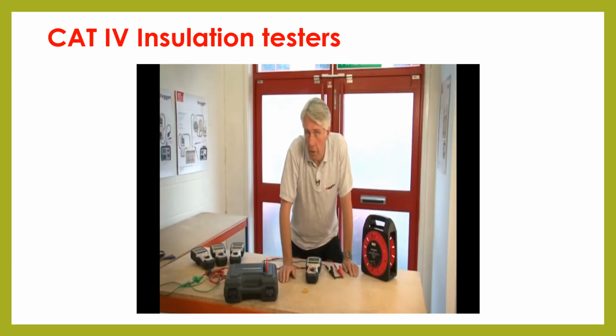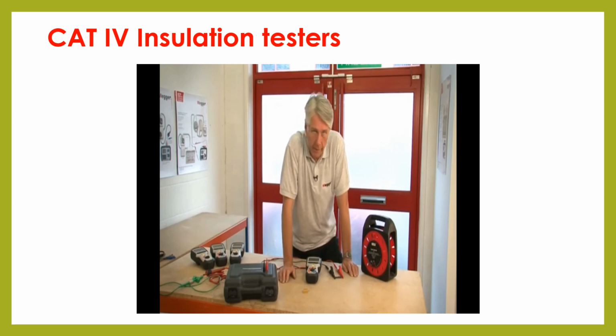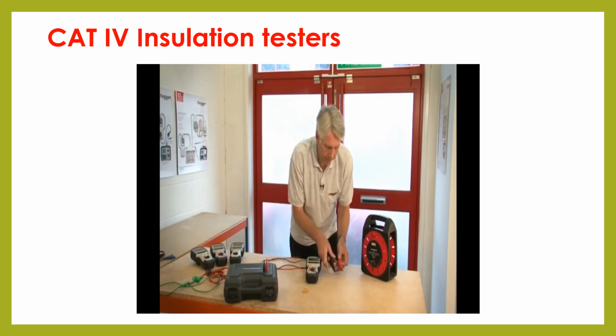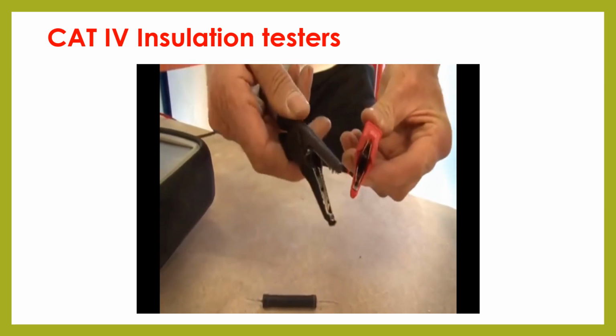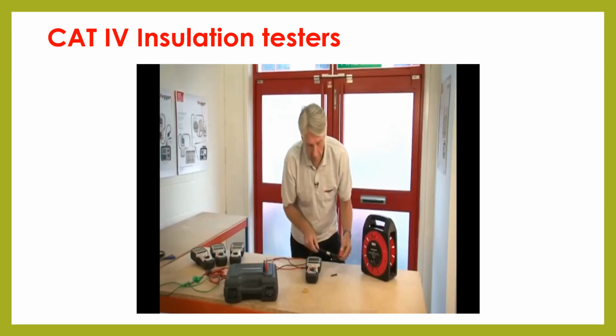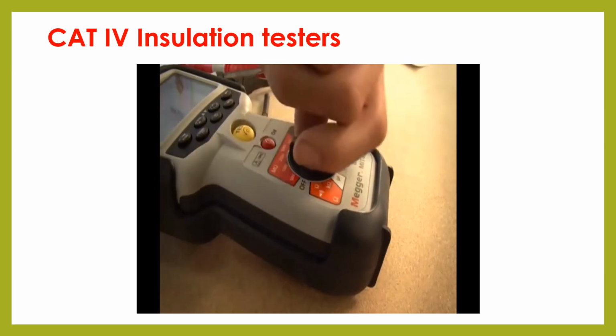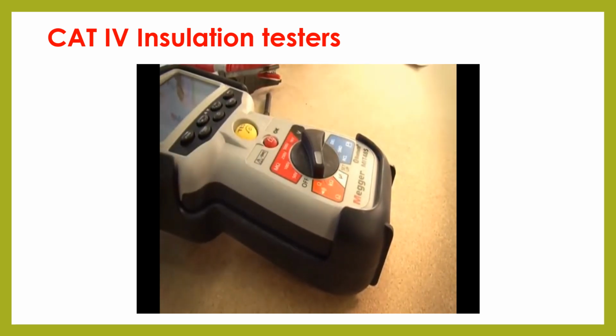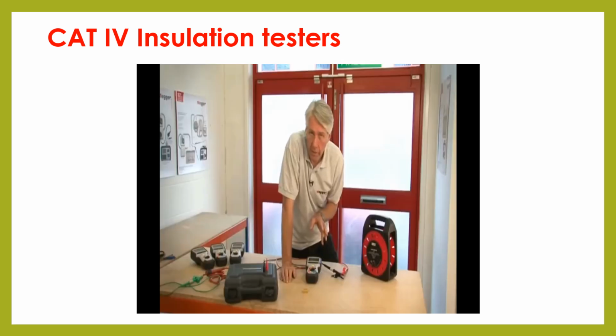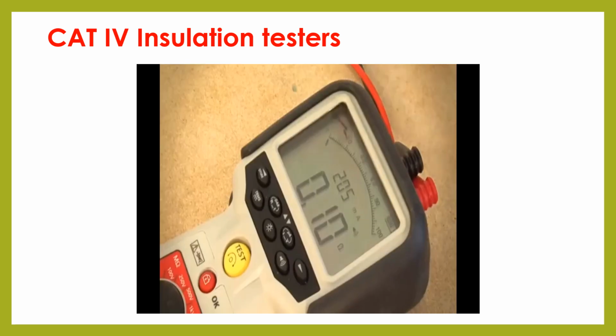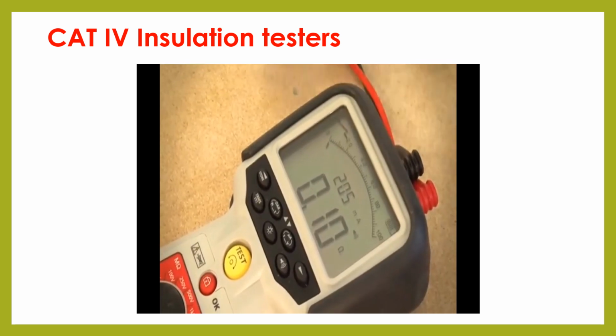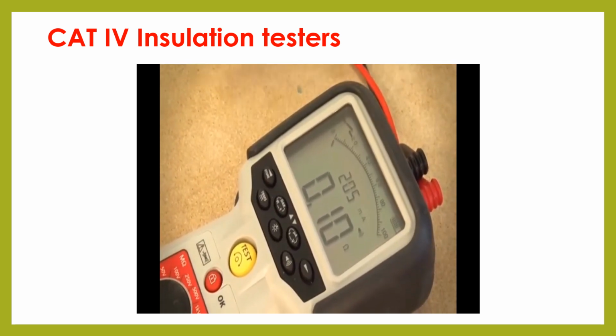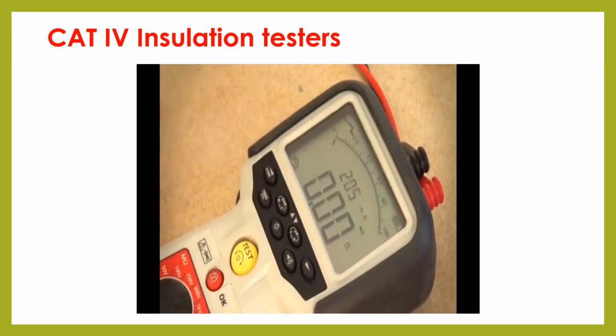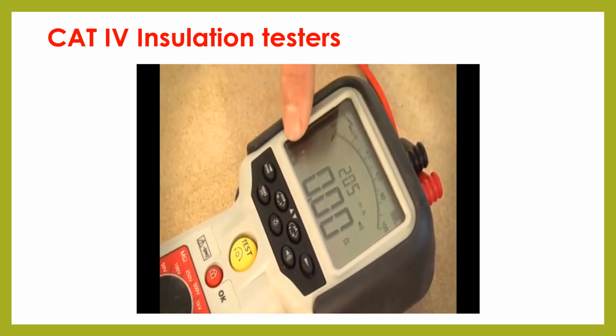Now let's look at the continuity measurement range with the buzzer. To measure continuity, you should first null out the test leads. To do that, we connect them together with a path of minimum resistance, and we select the continuity range. You can hear the buzzer because the leads are connected together. So we can see a reading of 0.01, which is the resistance of the leads, but if we press the test button, we'll null that out and we can see the null symbol has appeared in the display.